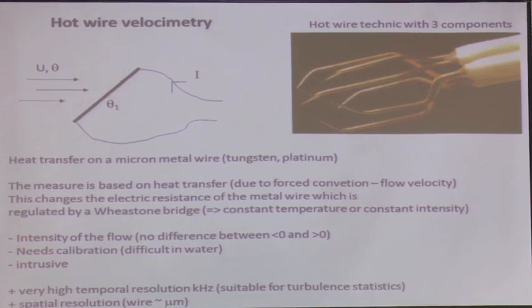Of course, it needs calibration, like many of them, but that one is pretty difficult, and specifically in water. In air, it's okay, but in water, there is a bias in time which is quite difficult to control. And of course, it is intrusive, because you need to place this wire into the flow.